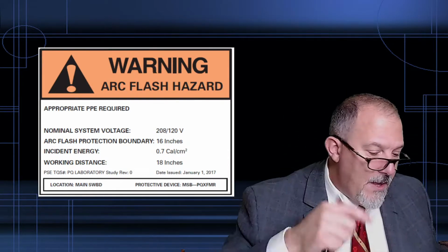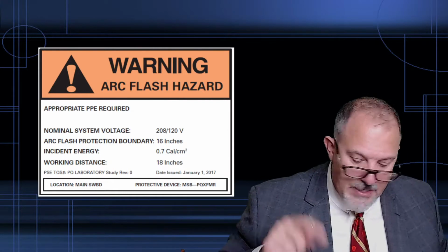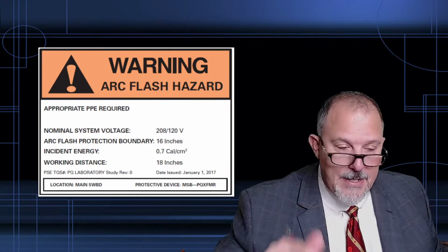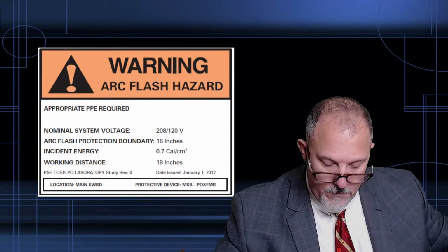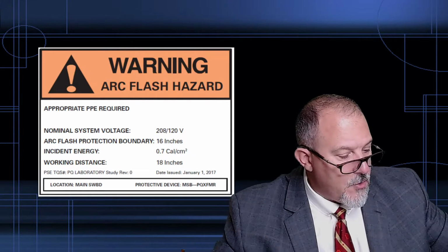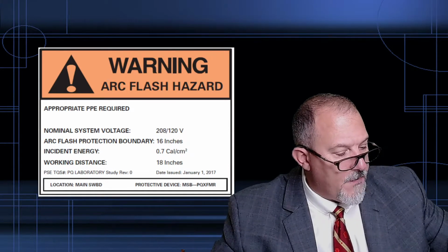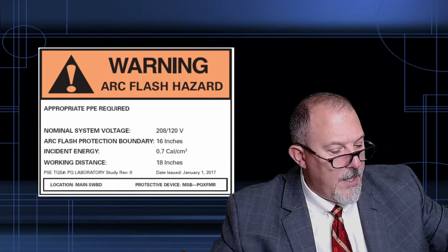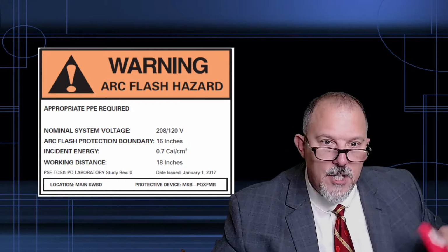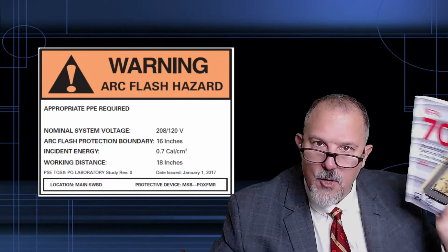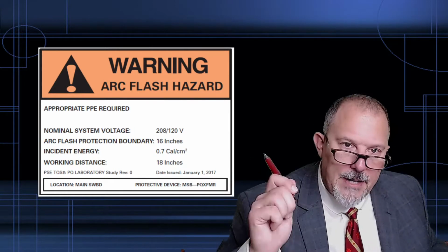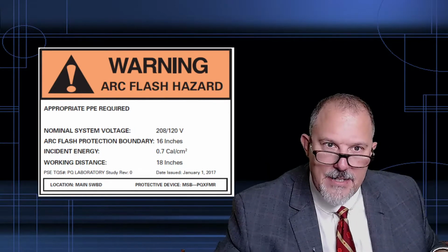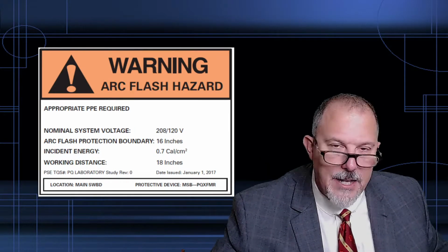Now, the way this exception is written in the 17 code, it says service equipment labeling shall not be required if an arc flash label is applied in accordance with the acceptable industry practice. So 70E does not require a date. If you get a label like this that doesn't have a date, it doesn't violate the National Electrical Code.